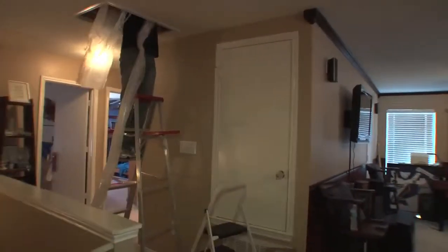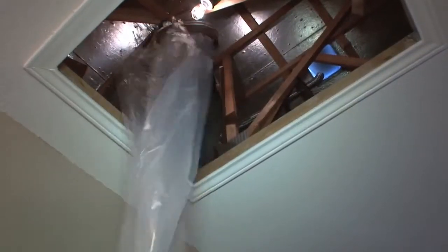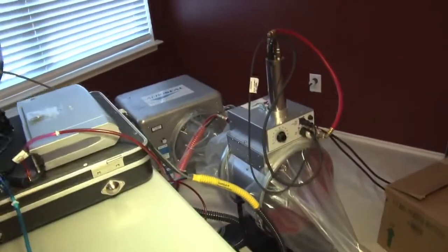When ductwork leaks, what that does is it puts the house under negative pressure. Your fan only knows one speed at the air handler, and it will suck air from wherever it can get it, so that it can do the makeup air for all the air that's leaking outside of the air-conditioned envelope. That's one of the reasons why houses are humid. Some of the most average complaints from our customers are inconsistencies in temperature, rooms in their homes that will not get very cold. In the summer, we have hot summers here, and having rooms that don't get cold with their AC, lots of dust in the homes, and high energy bills, but most of it's air quality.